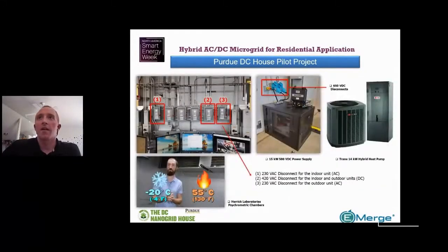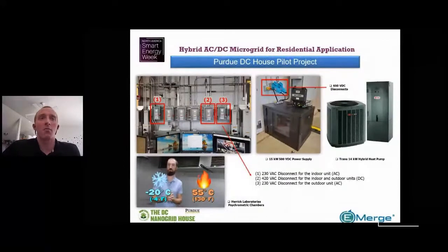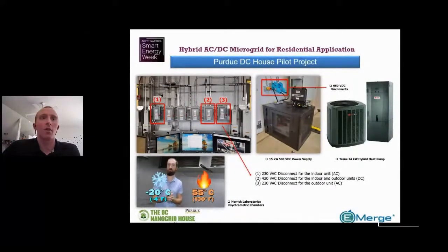On the next slide, here's a picture of our psychrometric chambers here at Purdue University. We have a 500 volt DC, 15 kilowatt power supply and a heat pump unit that was graciously retrofitted to consume direct DC power. We have this set up in our psychrometric chambers so we can test it under all kinds of environmental conditions, both indoor and outdoor. Our chambers can go from -20 degrees Celsius all the way up to 130 degrees Fahrenheit, so we can test a huge variety of conditions.